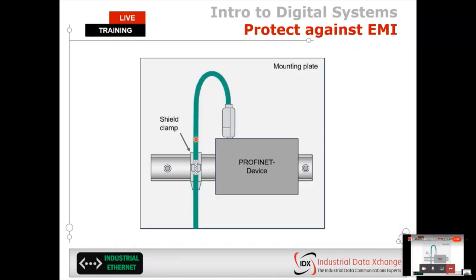Very good practice, beyond obviously having to use shielded Ethernet cable in industrial Ethernet, is that this shielded cable needs to be grounded at multiple points, mainly at two points: at the device itself, where you're using an industrial Ethernet connector that has a metal housing. This will drain any noise picked up in the field from the shield to the DIN rail through the device, or through a separate functional bonding connection.